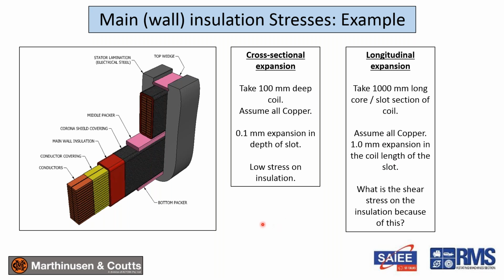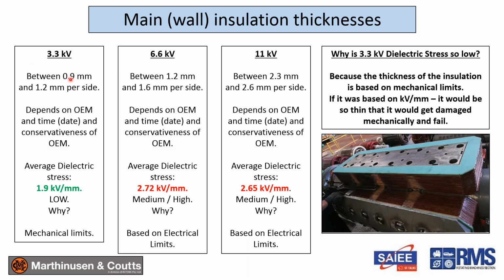Now imagine that 1 millimeter over the thickness of the main insulation, which you'll see now. 3.3 kV is typically between 0.9 and 1.2 millimeters per side, 6.6 between 1.2 and 1.6, 11 kV between 2.3 and 2.6. This varies depending on certain things, like I said, resin rich versus global VPI, but I've tried to look at a decent average. So now let's look at the average dielectric stress on a 3.3 kV machine. It's 1.9 kV per millimeter, which is low. The normal range is between 2 and 3. A lot of OEMs push a lot higher than 3 today. 6.6 kV, 2.7 kV per millimeter. So it's medium to high. And 11 kV is 2.65. So it's also round about the same as the 6.6 kV.